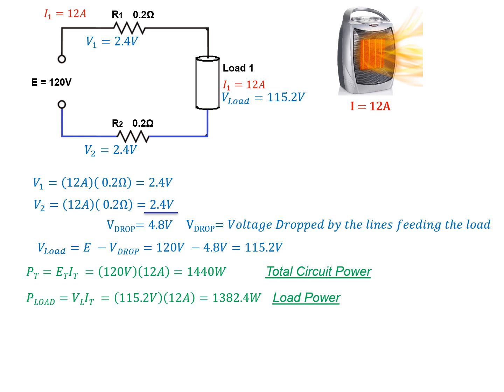That's because our feeder wires are actually going to heat up. Because it's a resistance and because current is flowing through that resistance, those wires are actually going to generate a little bit of heat. We call that the line loss or line loss power. That's the difference between how much our source is putting in and how much our load is actually able to dissipate. That's also the reason why we have to be careful when we're installing wires, such as putting wires in conduit. If we put too many wires in conduit, then each of those wires is acting like a little heater and they're going to generate heat or dissipate power. You have to compensate or allow that heat to escape. You have to manage that heat if you wish.